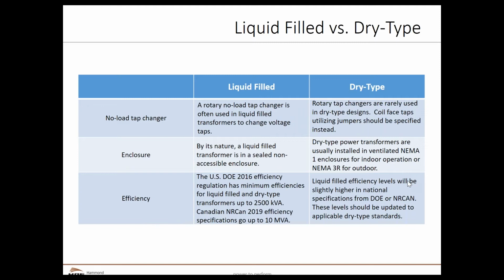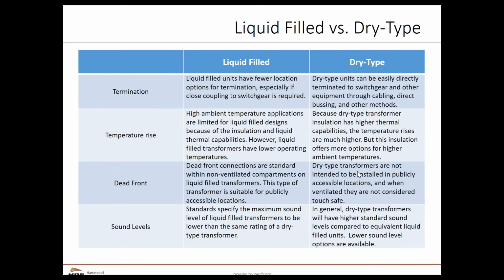Efficiency, there are different efficiency levels for liquid filled versus dry type. The efficiency levels, actually not generally, always for liquid filled, will be a little bit better, a little bit higher efficiency levels than the dry type. And we've addressed that earlier. Terminations, liquid filled have fewer options for terminations. Again, generally you have a front mounted wiring compartment, and all terminations have to be within certain locations in that small wiring compartment. With a dry type transformer, you have a much larger ability to bring in stuff from below, from the roof, from the sides than you do with the liquid filled. So again, a lot more flexible in the cabling and busing methods for a dry type.